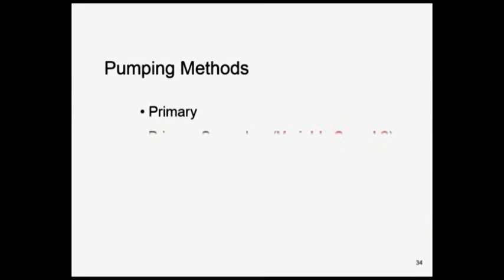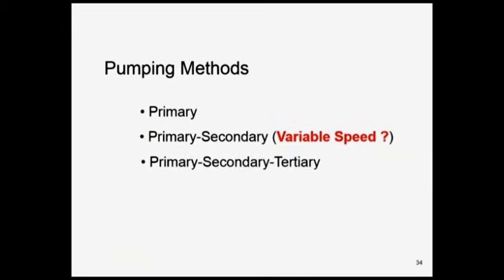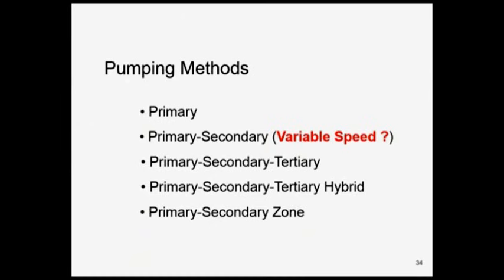Primary pump we just talked about. Primary, secondary, by the way, primary, secondary pumping is beginning to use variable speed on the primary and variable speed on the secondary. You're going to begin to see a lot of that coming. Primary, secondary, tertiary, tertiary hybrid, where you've got a little combination of both. It's important you catch that you see this. There's nothing wrong with that design. In fact, it's a good design, where the building closest to the chiller plant may not need an extra pump. And then primary, secondary, zone pump, the distributed pump.